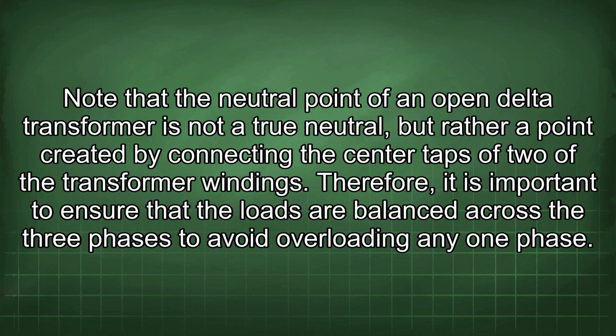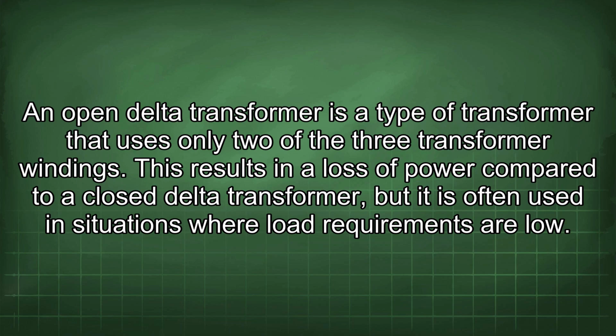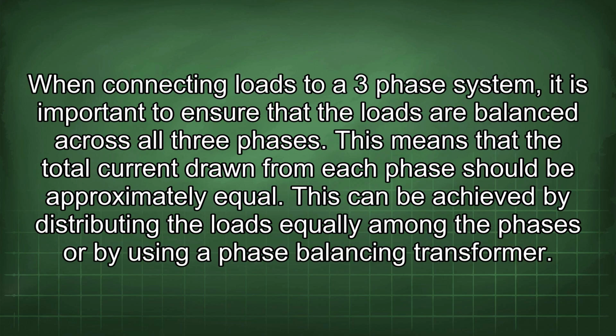Therefore, it is important to ensure that the loads are balanced across the three phases to avoid overloading any one phase. An open delta transformer is a type of transformer that uses only two of the three transformer windings. This results in a loss of power compared to a closed delta transformer, but it is often used in situations where load requirements are low. When connecting loads to a three-phase system, it is important to ensure that the loads are balanced across all three phases. This means that the total current drawn from each phase should be approximately equal. This can be achieved by distributing the loads equally among the phases or by using a phase balancing transformer.